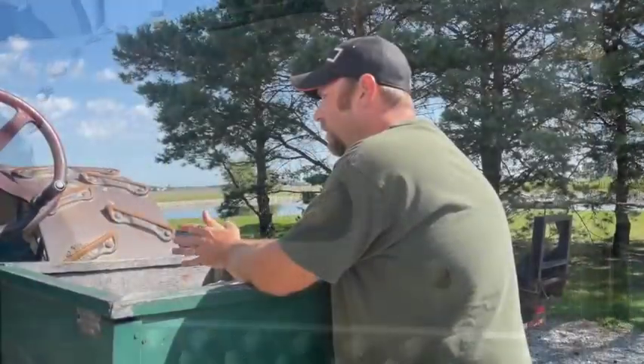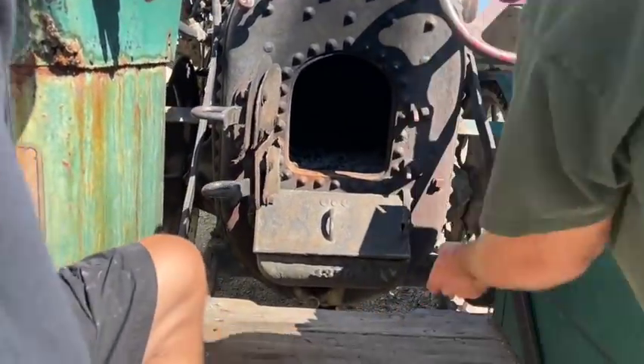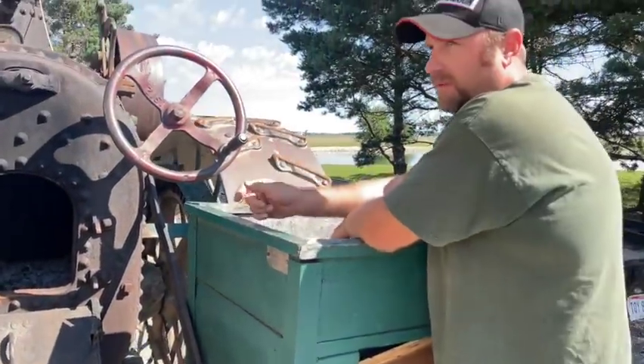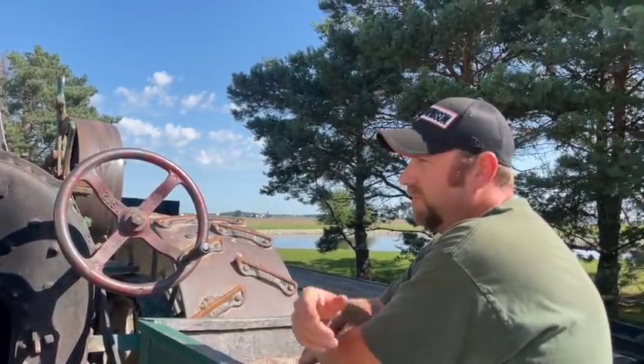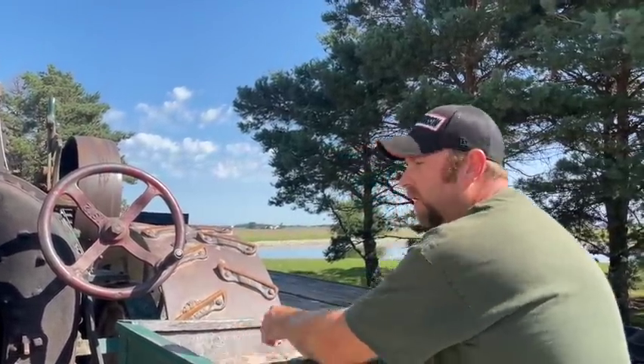You look at the boiler. This one doesn't have it because this is a dry bottom. It's got one handhole down here, like clean out plates to clean out your boiler. Some of them have been sitting for 60, 80 years. They'll leave those handhole plates in there, and it'll just be full of scale, or you can see mud in there. Then that obviously will hold the moisture, and it just rots the boiler out.